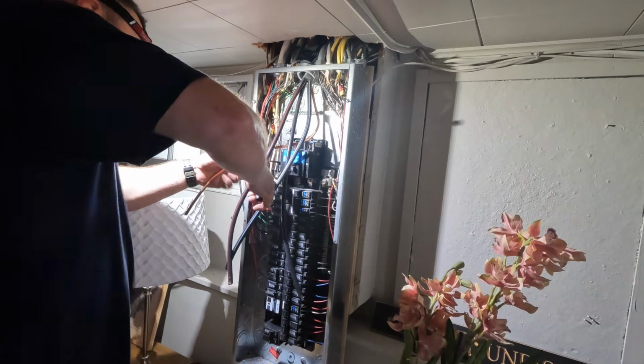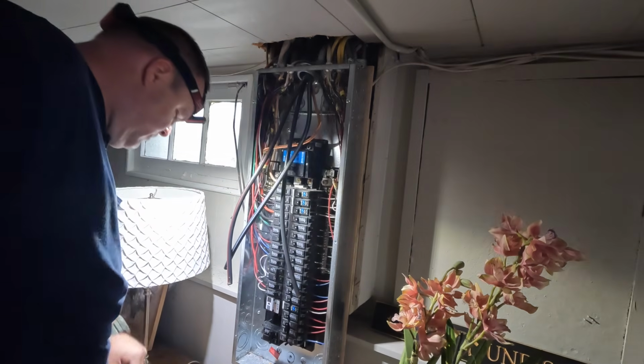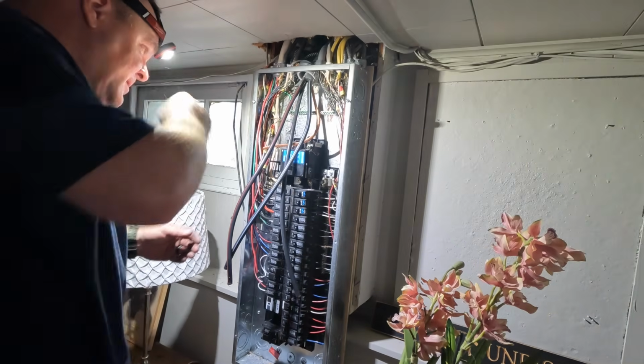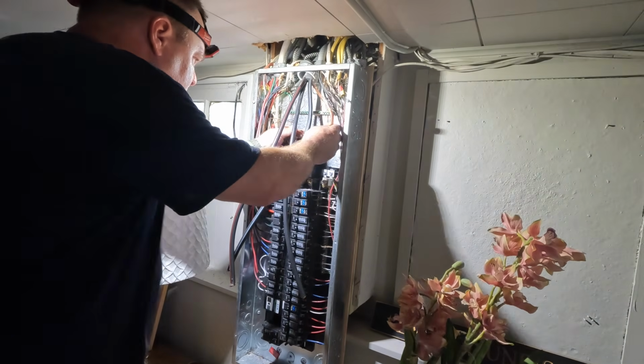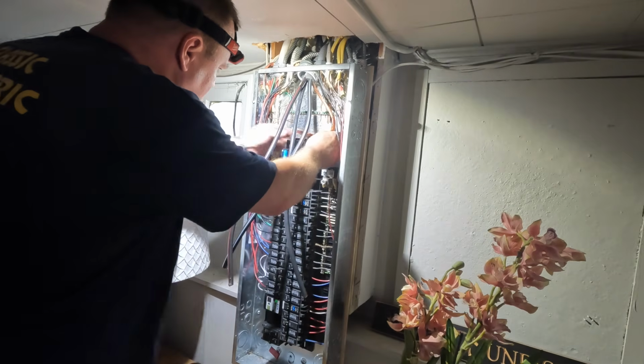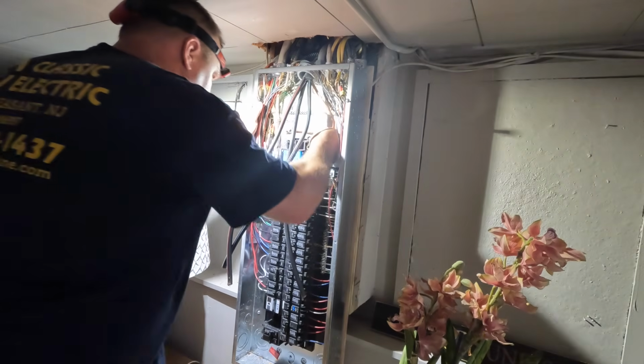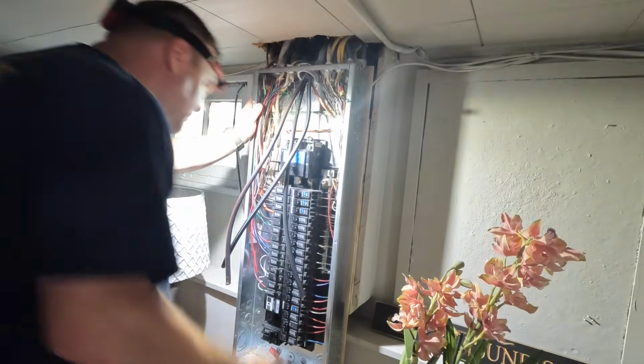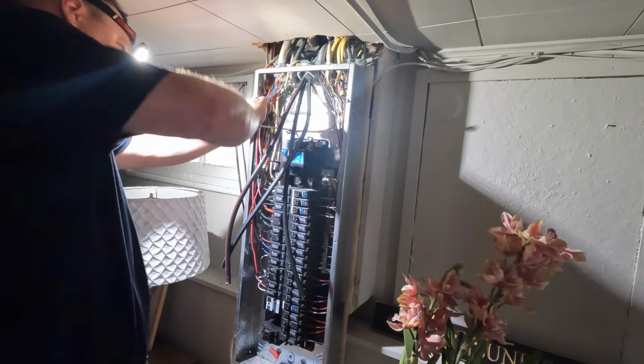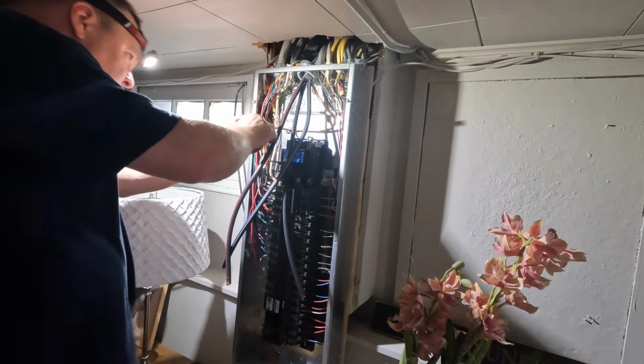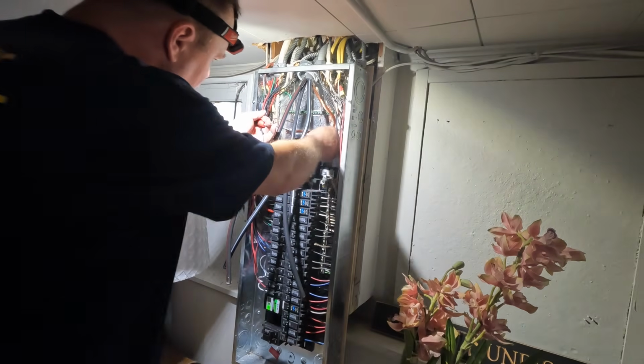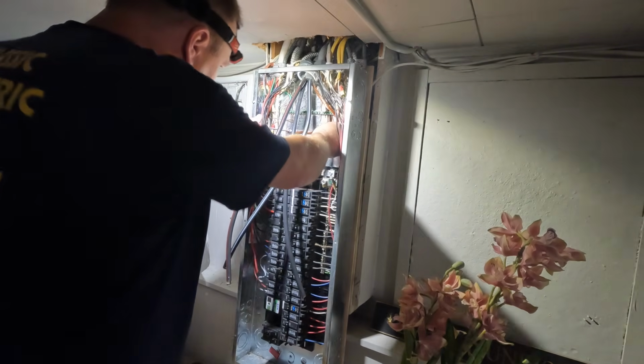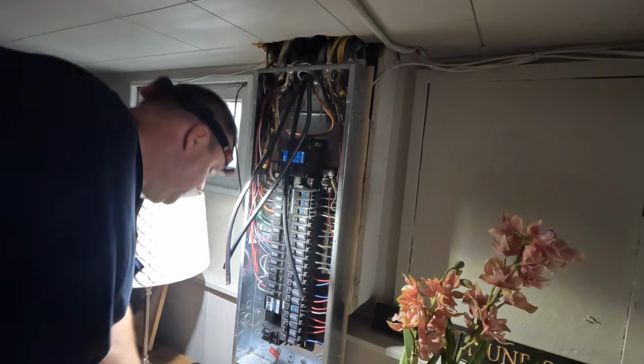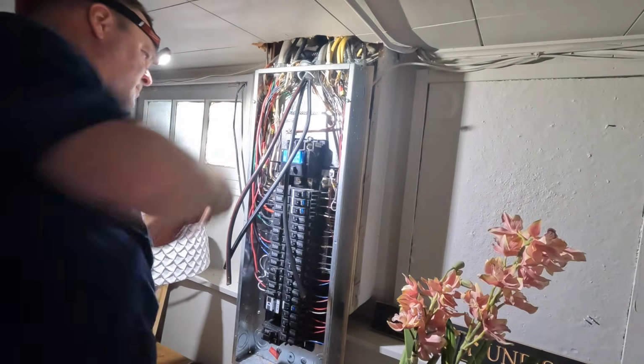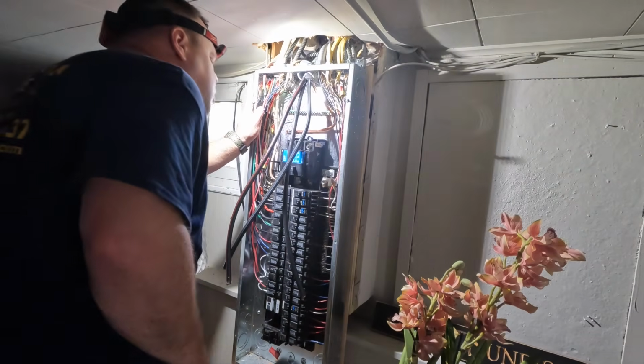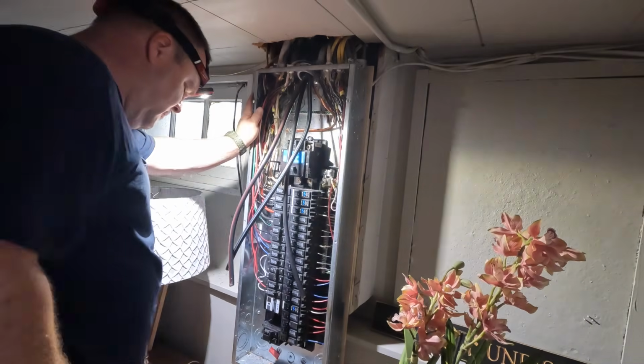neutral conductors, okay? And so inside, I've been over this before, the grounded neutral conductor is a current carrying conductor in most cases. Now there are some exceptions, which we're not going to get into in this video, where you do not count that as a neutral conductor. But for the most part, the grounded neutral conductor, the majority of the time, is a current carrying conductor. And the neutral current will knock you on your ass just as well as an ungrounded conductor will, should you connect that to ground. So we're isolating it here so we don't have any objectionable current flow, Article 250.6, flowing on our equipment grounding conductors or any of our piping or anything that's grounded within the house.